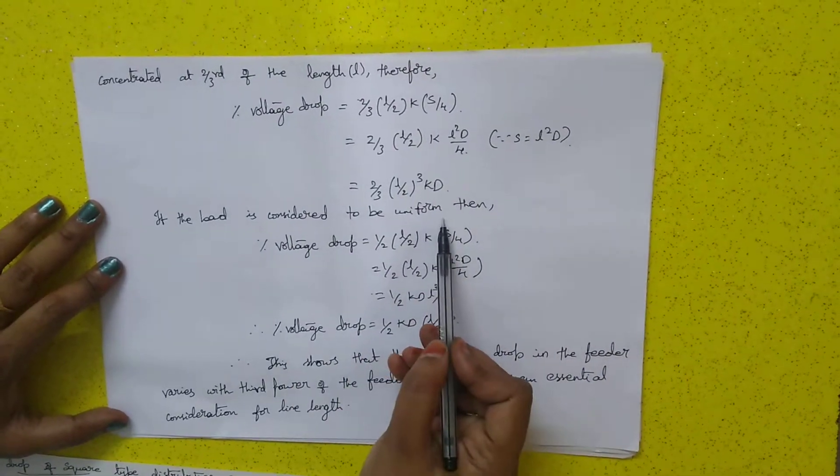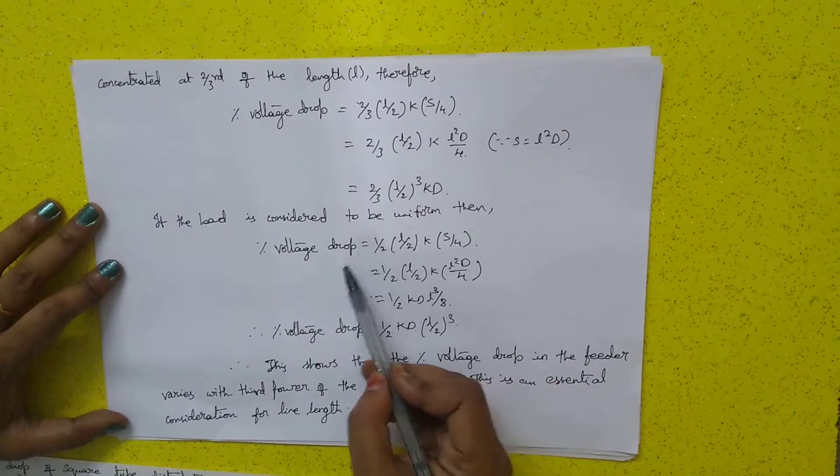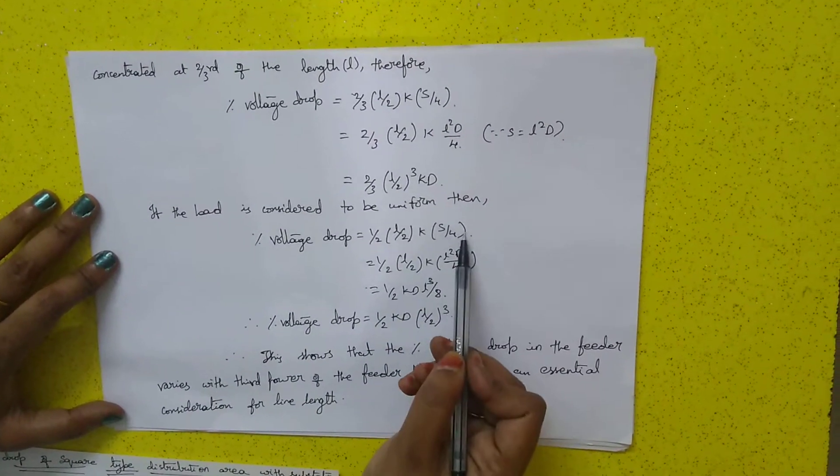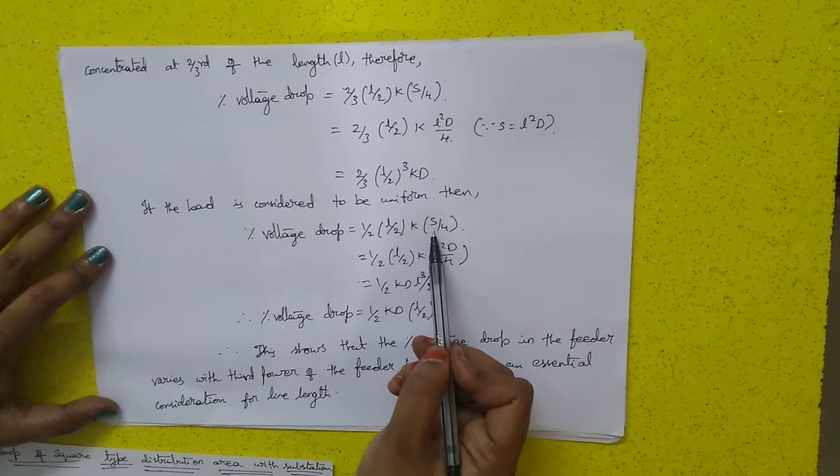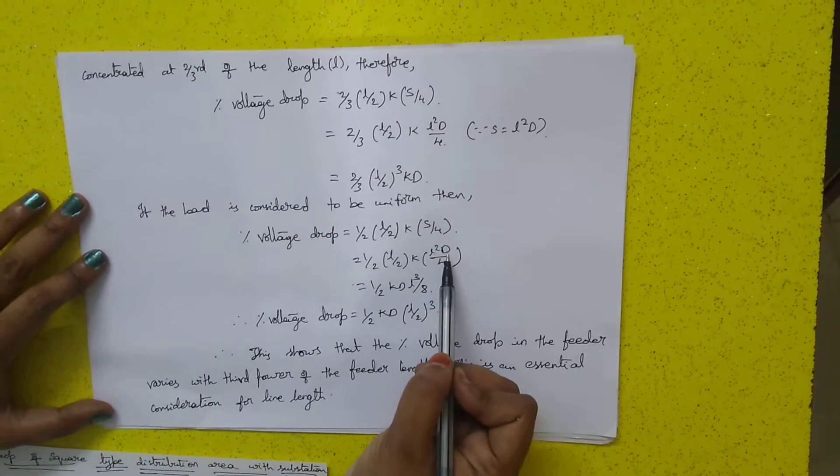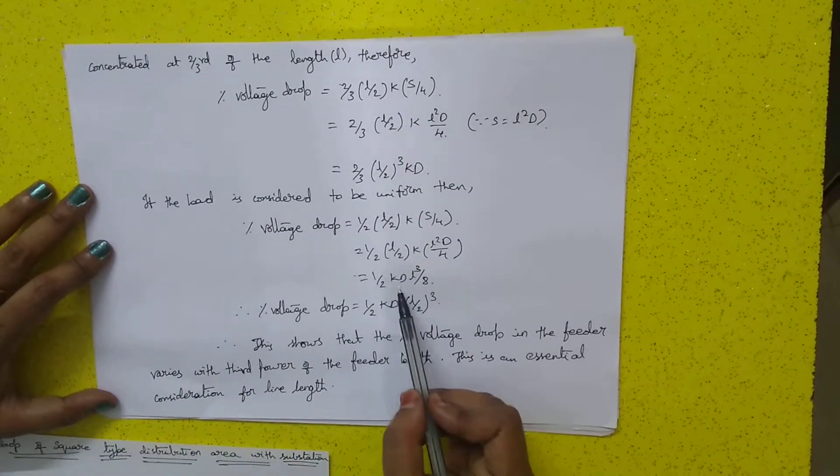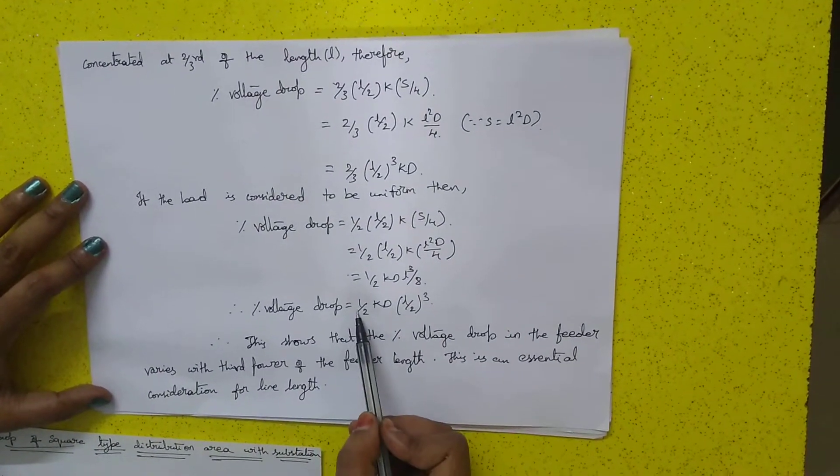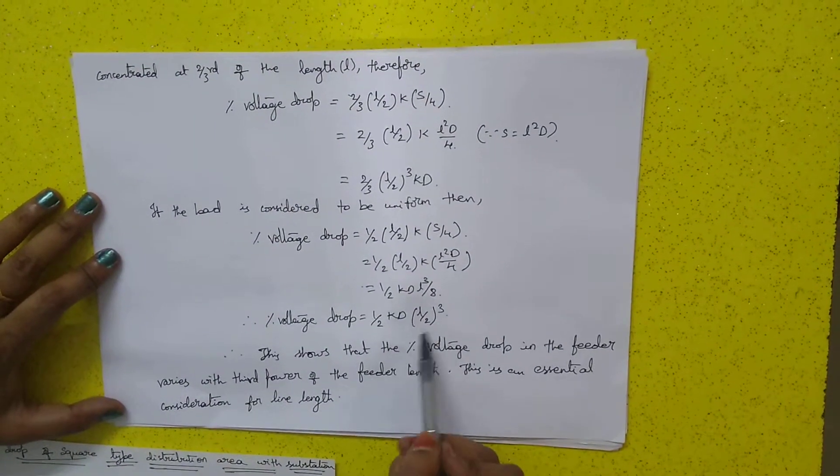If the load is considered to be uniform, then the percentage voltage drop will be half of L by 2, k, s by 4. We know that s equals L-square d. Substituting s equals L-square d in this equation, we obtain half k into d into L-cube by 8. Therefore, the percentage voltage drop equals half k into d into L by 2 whole cube.